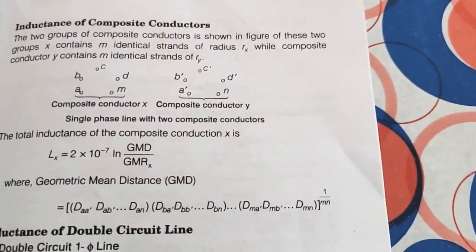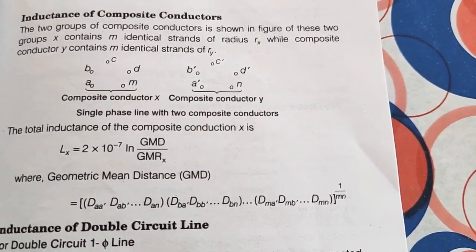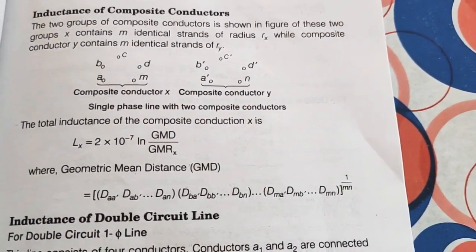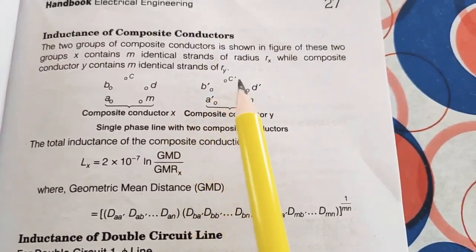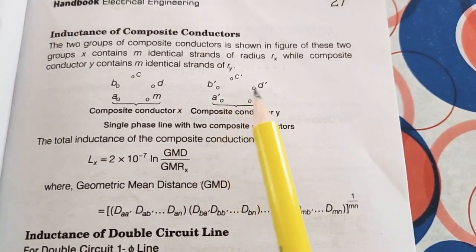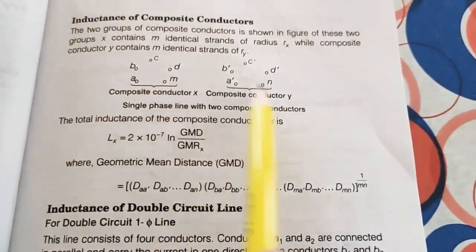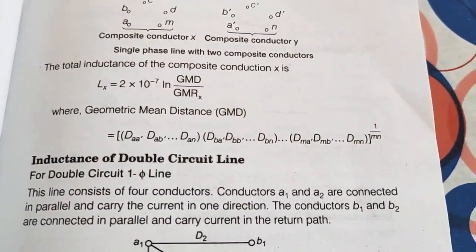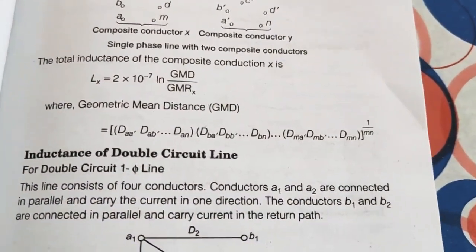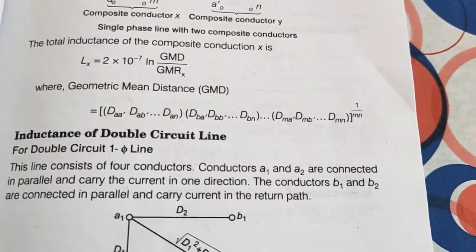For inductance of a composite conductor, two groups of conductors: group X contains M identical strands of radius R-X, and composite conductor Y contains N identical strands of radius R-Y. Inductance L-X equals 2 into 10 to the power minus 7 times ln(GMD/GMR-X) Henries per meter, where GMD is computed from distances D-A-A-dash, D-A-B-dash, etc.